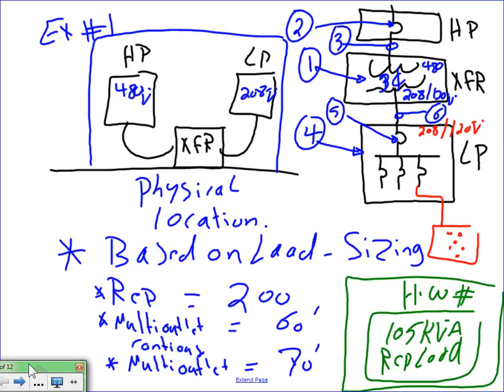You remember when we went to Boston Scientific? Did you see where it says HP and LP panels? That's exactly what you're looking at. HP is high voltage, LP is low voltage. You have a 480 volt system, almost always 480 for this panel, through a transformer down to 208. Typically, 90% of the time in the US, you're going to find this scenario. The reason is that we haven't decided in the US to get rid of the 120/208 and go to 230. So we can't burn the receptacles at 277, so you have to burn them at 120.